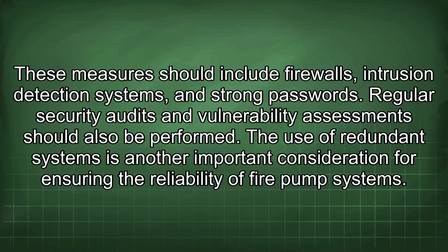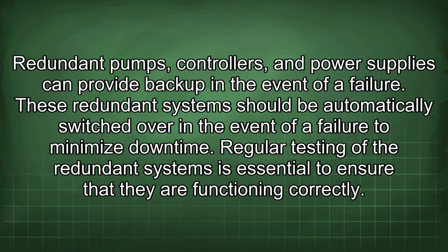The use of redundant systems is another important consideration for ensuring the reliability of fire pump systems. Redundant pumps, controllers, and power supplies can provide backup in the event of a failure. These redundant systems should be automatically switched over in the event of a failure to minimize downtime. Regular testing of the redundant systems is essential to ensure that they are functioning correctly.